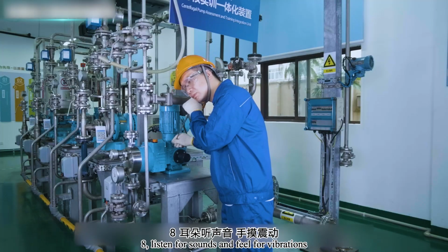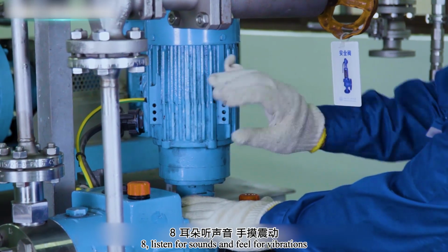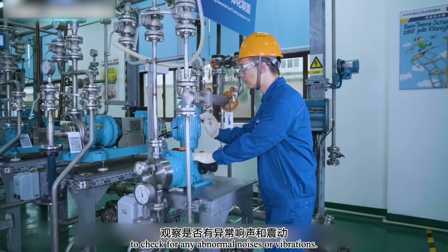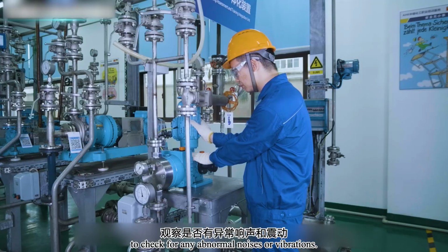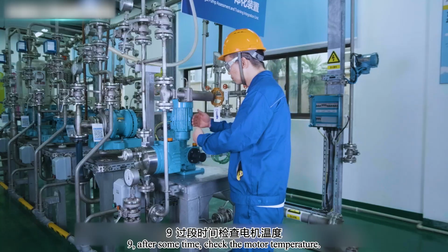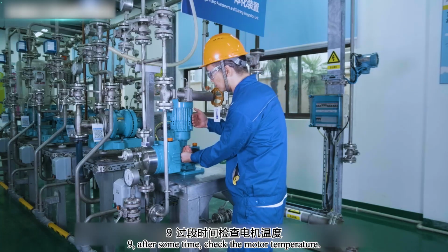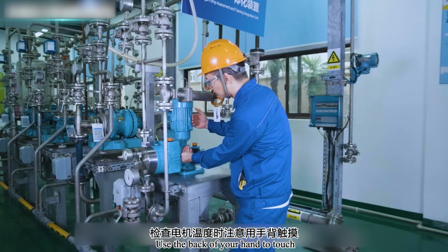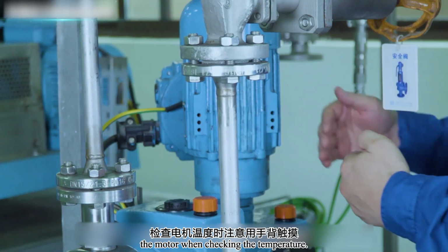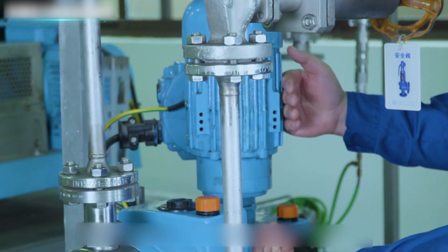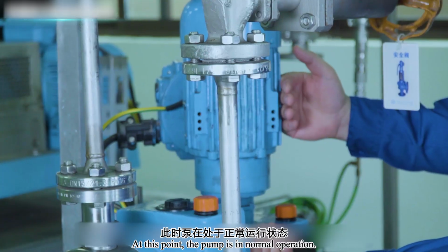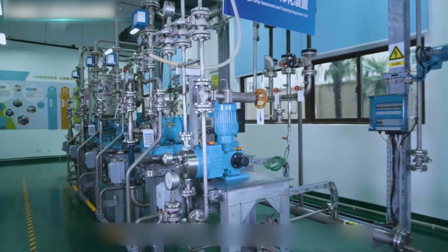Eighth, listen for sounds and feel for vibrations, to check for any abnormal noises or vibrations. Ninth, after some time, check the motor temperature. Use the back of your hand to touch the motor when checking the temperature. At this point, the pump is in normal operation.